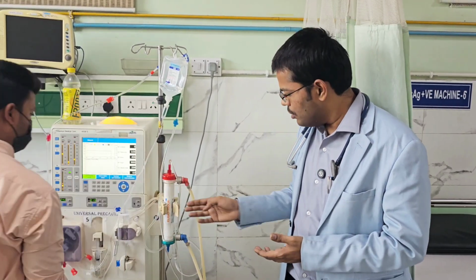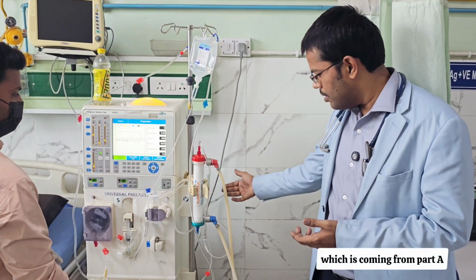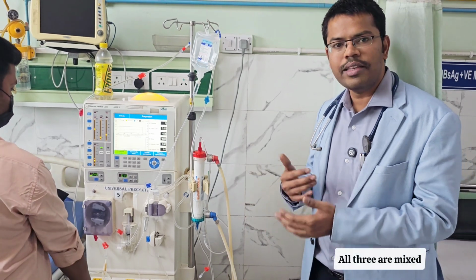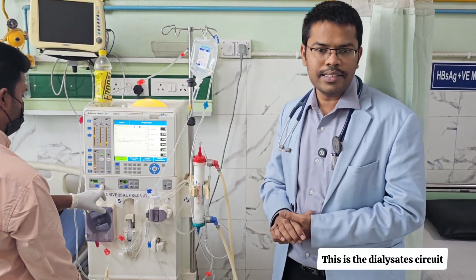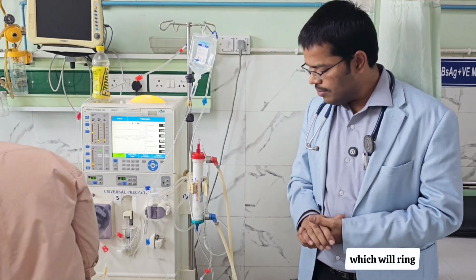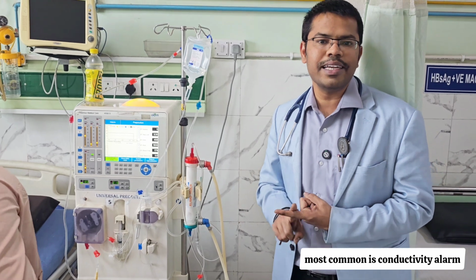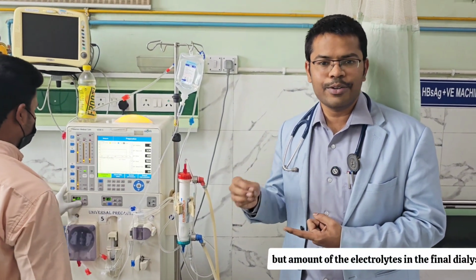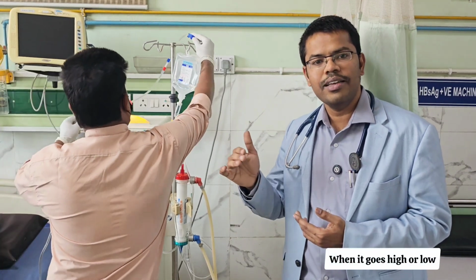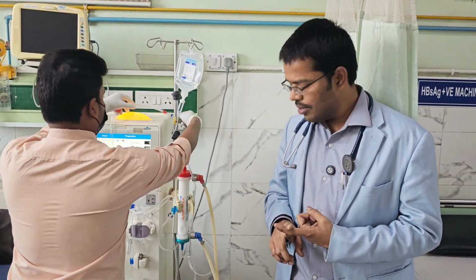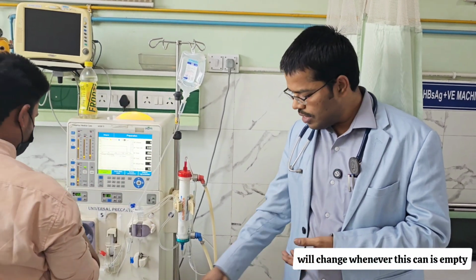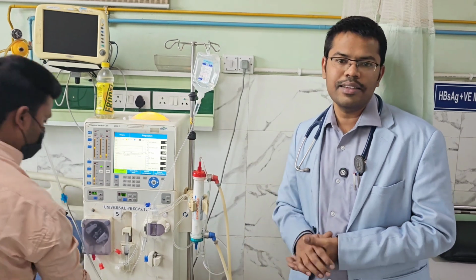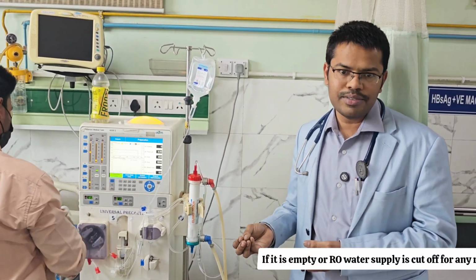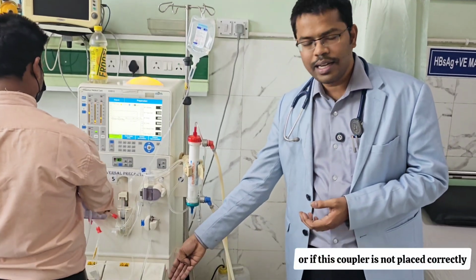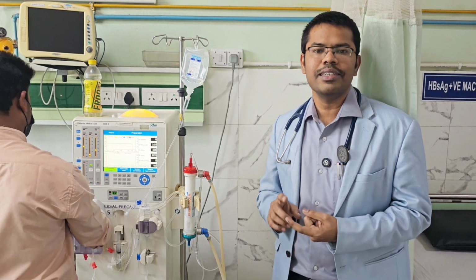Now coming to the specific ones, dialysate circuit related. As you know, this is the dialyzer, and this is the dialysate which is coming from part A, part B and water. All three are mixed and the dialysate is coming. This is the dialysate circuit. So what are the alarms which will ring when there is a problem? The most important and most common is the conductivity alarm. Conductivity is nothing but the amount of electrolytes in the final dialysate. When it goes high or low, the conductivity alarm will ring. When does conductivity most commonly change? Whenever the part A or part B can is empty, or the RO water supply is cut off for any reason, or the coupler is not placed correctly, conductivity goes down and the conductivity alarm will ring.